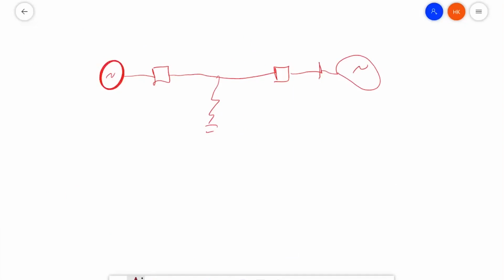Okay, so briefly I'm going to talk about just how the traveling waves work and how we see them in our relay. So I just pulled up this whiteboard to have some more room to write. So if we've got this transmission line here, and we've got a fault somewhere on the line, we're going to see traveling waves launched from the fault point to each terminal. And right now I'm just going to talk about the current traveling waves. So we're going to have a relay at each end. And when the waves are launched from the fault point, they're going to start moving towards each terminal.